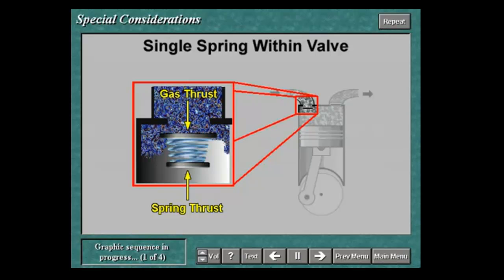The valve, however, must close just at the end of the stroke, whether it is a suction or discharge valve. If spring stiffness and ring lift or gas velocity are not correctly related to each other, the rings are not stable and will flutter.